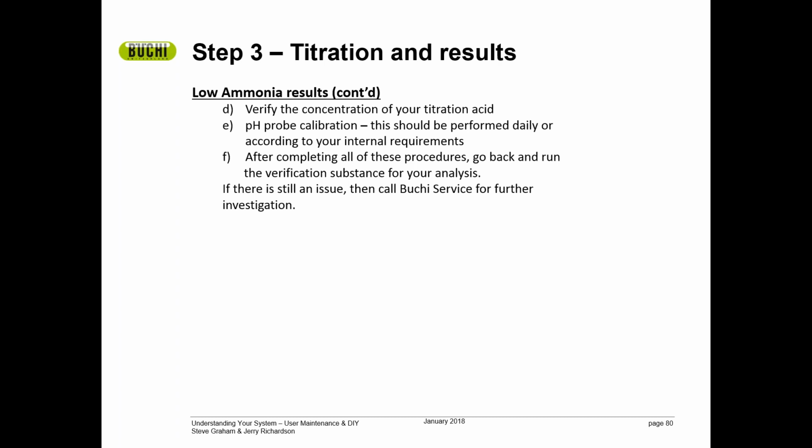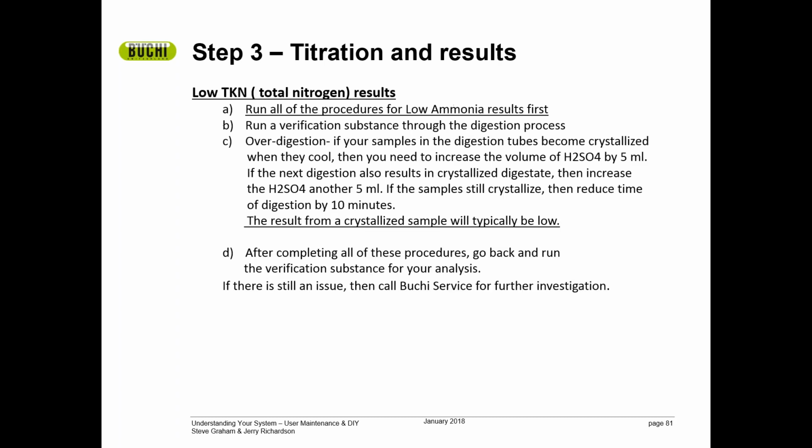After completing all these procedures, run the verification substance again. If you still have a problem with low nitrogen, you need to call us at Buchi Service and we'll do further investigations with you.